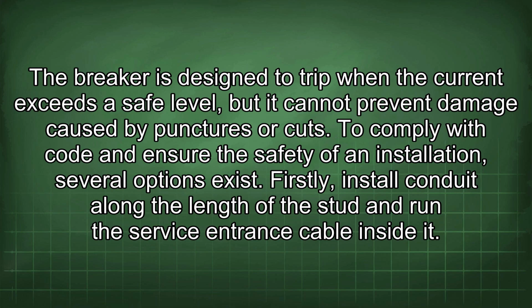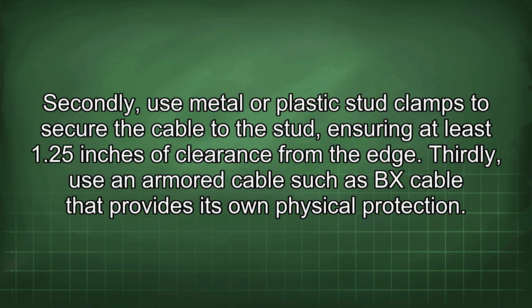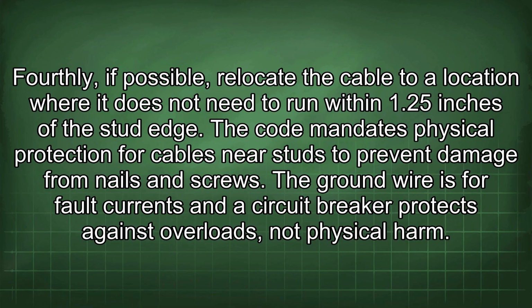Firstly, install conduit along the length of the stud and run the service entrance cable inside it. Secondly, use metal or plastic stud clamps to secure the cable to the stud, ensuring at least 1.25 inches of clearance from the edge. Thirdly, use an armored cable such as BX cable that provides its own physical protection. Fourthly, if possible, relocate the cable to a location where it does not need to run within 1.25 inches of the stud edge. The code mandates physical protection for cables near studs to prevent damage from nails and screws.